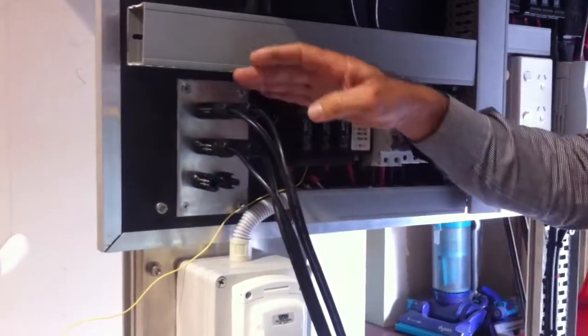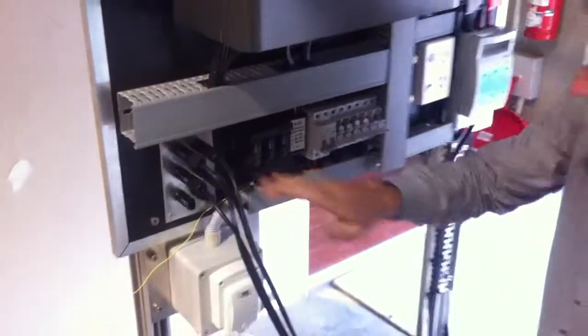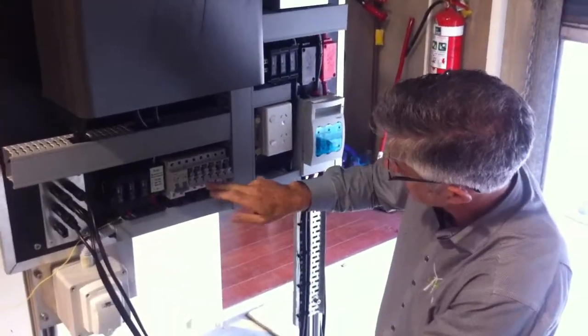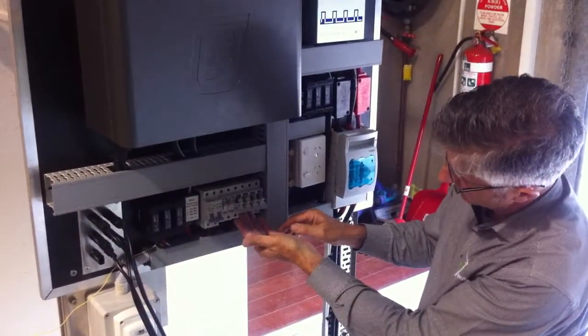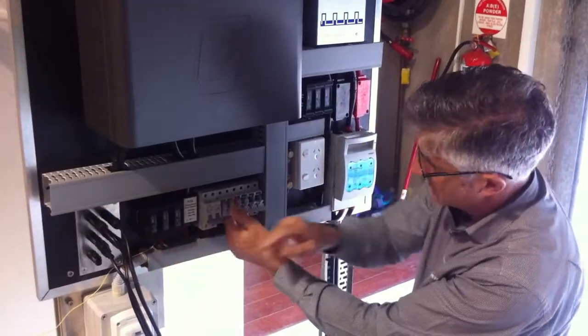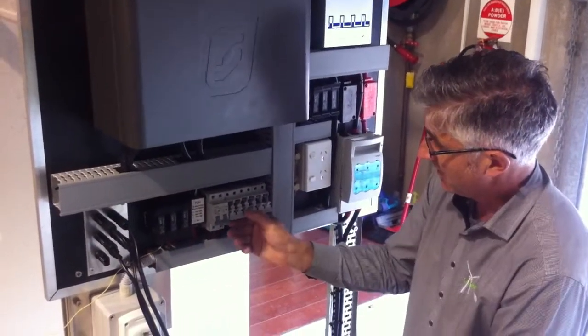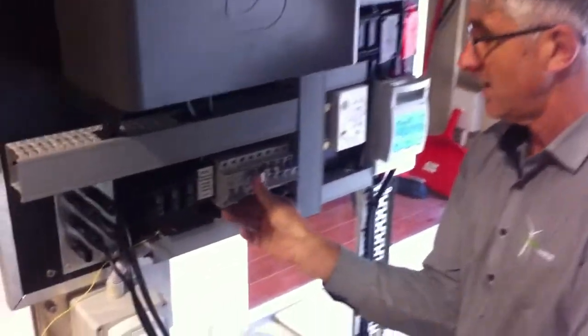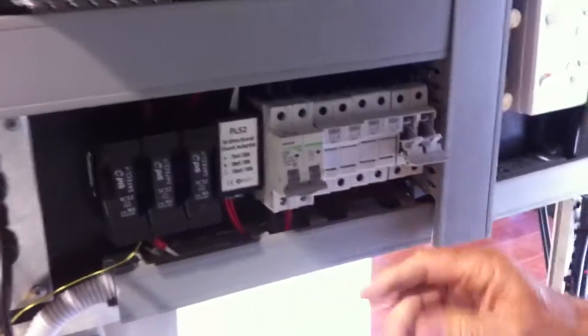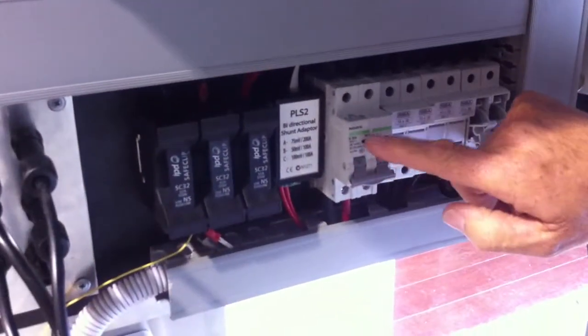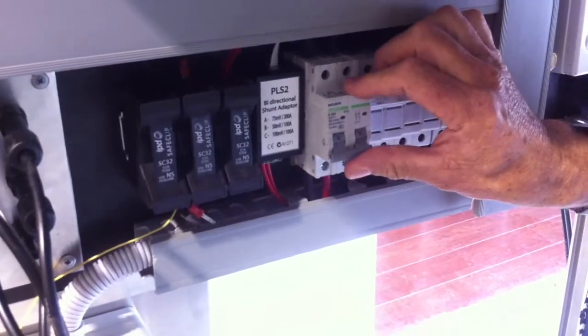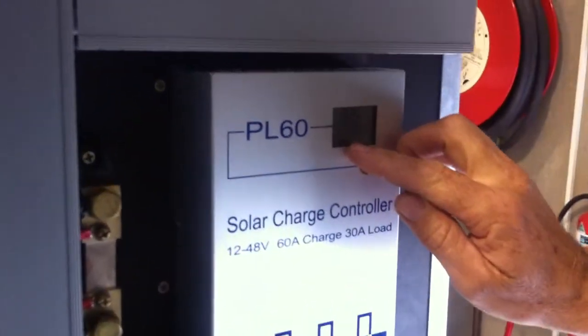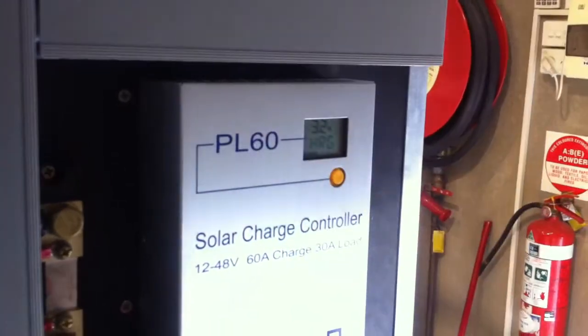So now we've got your solar array voltage running from here across to the bottom of your fuses. These are what we call string fuses - each one is separately fused. If we close those over now, close your fuses over, switch on the array isolator like so, and come back up to the PL60 and click through till you see charge, you'll notice we've got 3.2 amps of charge going in.